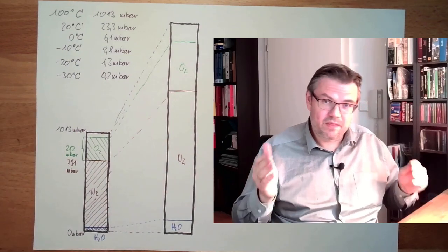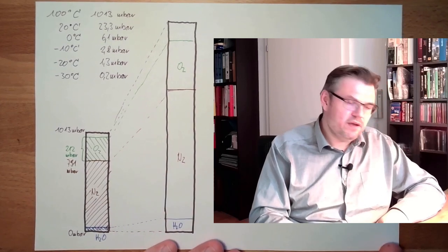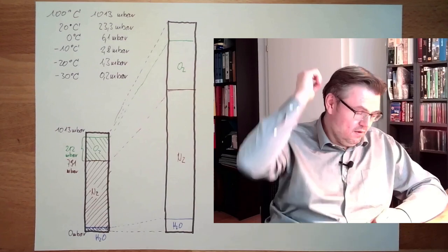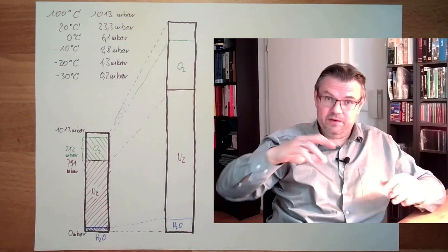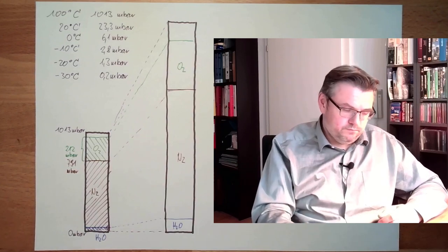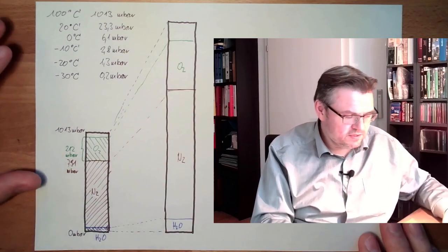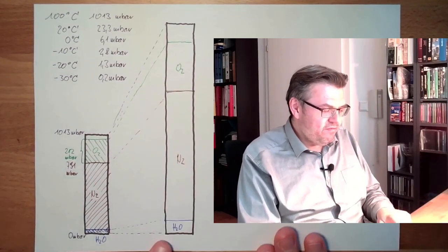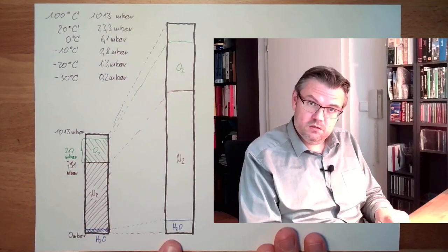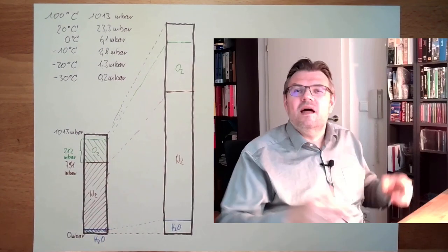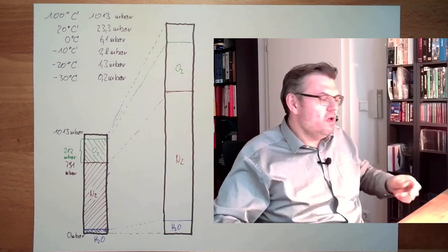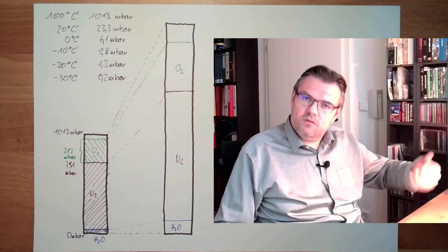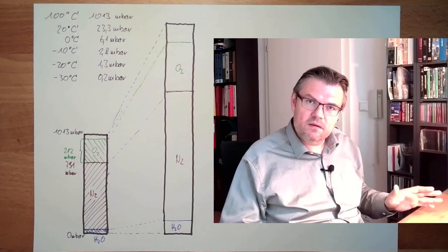This is why we usually have in pressure vessels somewhere a condensate trap. We need to relieve the condensate. And of course, if this is then going somewhere into the system, I might get a problem there, because suddenly water is in the system. This means I have to dry the air after compression. In standard compressors at home, you usually have this condensate trap, you open it, water is coming out, you close it, from time to time you open it, you're fine.